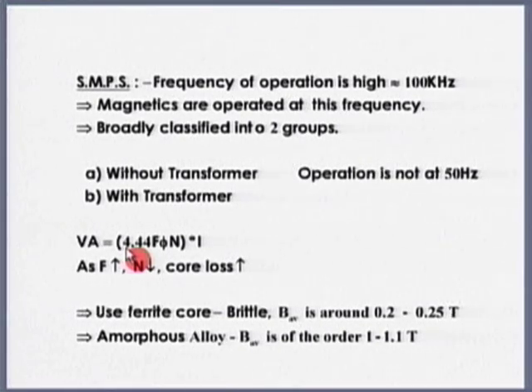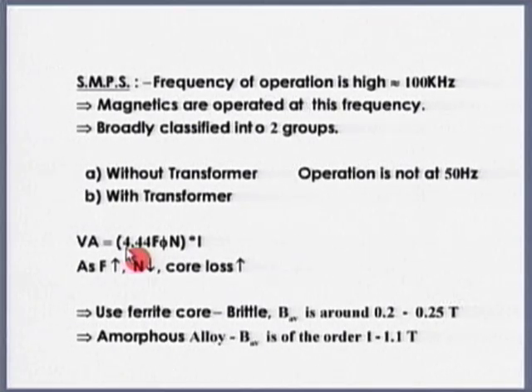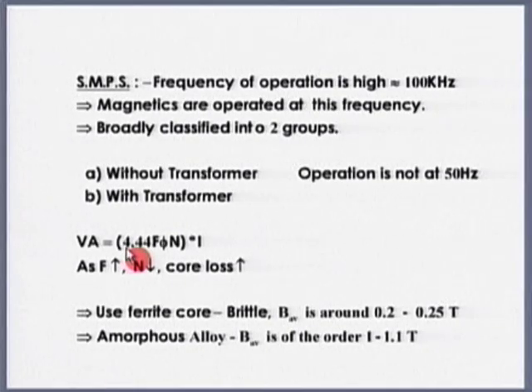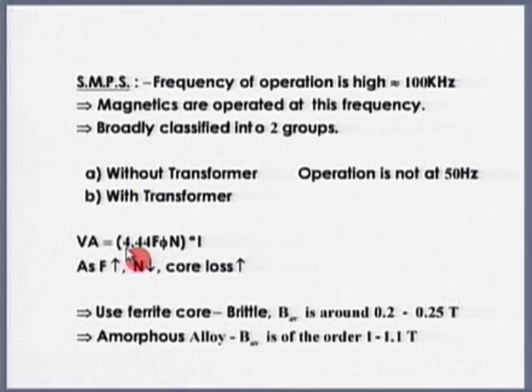The problem with the ferrite core is that it is very brittle and the operating flux is very low — of the order of around 0.2 tesla. Of course, amorphous alloy cores are also now available, with average B of the order of 1.1 tesla. These two cores are popularly used in DC to DC conversion.